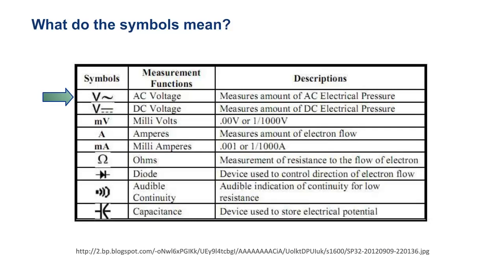The first symbol is AC voltage. It's a large V with an analog or sine wave behind it, designed to measure alternating current. Pretty much all of our pumps are going to be alternating current. It's going to give you a solid number. Always follow state, local and federal codes. Don't go where your licensing won't permit. We should only be measuring voltage at the back of the pump or at the pressure switch or the control, not beyond that. If you have questions or issues, don't be afraid to get an electrician involved. Always wear PPE, your personal protective equipment, and always be on your toes. Don't cut corners. Safety is a priority.